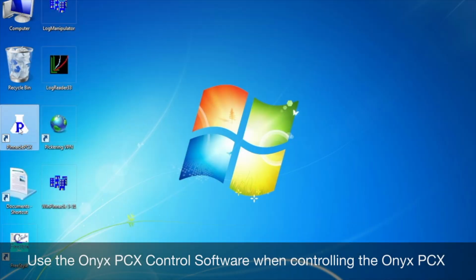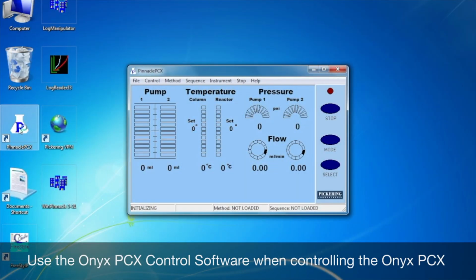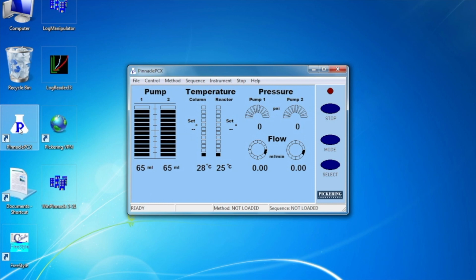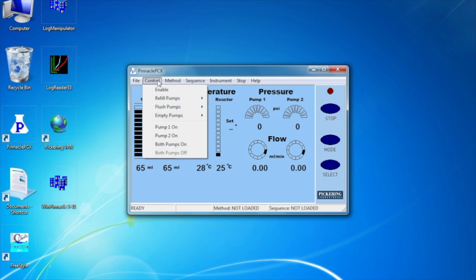Open the Pinnacle control software and wait for the ready status in the lower left corner of the window. Once the Pinnacle and the Pinnacle control software are connected, select empty pumps to remove any reagent left in the pumps and zero out the pressure transducer.